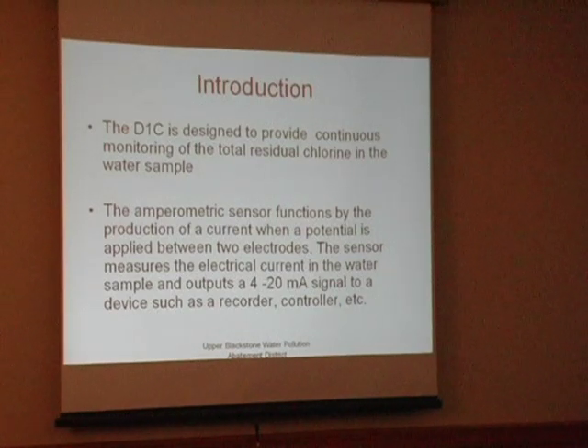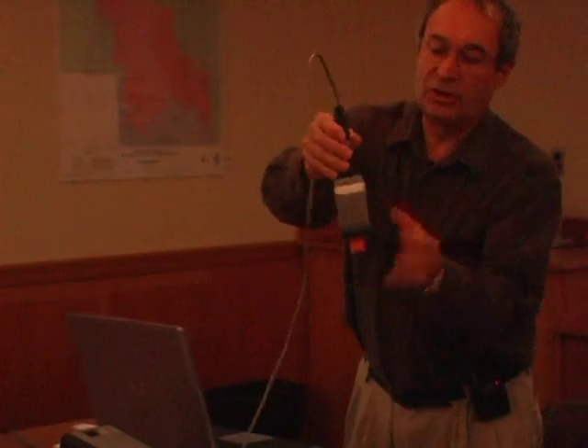between 2 electrodes. Now we have a sensor which is right here. This is a sensor in a holder, and we'll get into this a little bit later as far as what it really looks like and how it operates, but that's basically it. When chlorine is in water, an electrical current is generated based upon the concentration of that chlorine. This sensor is designed to pick that up. It converts that signal to a 4 to 20, which you could use to send to this instrument to display the chlorine concentration, to control your pump, to send it to a recorder, to send the signal to a SCADA system, which I think is the situation here, where that SCADA system then controls your operation.